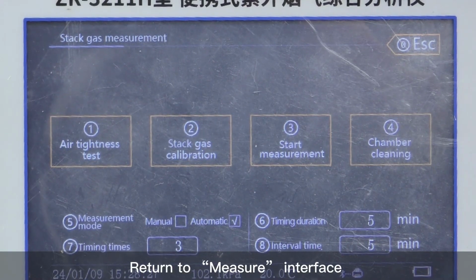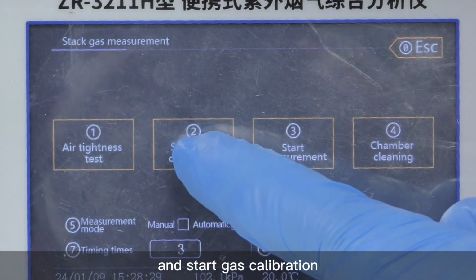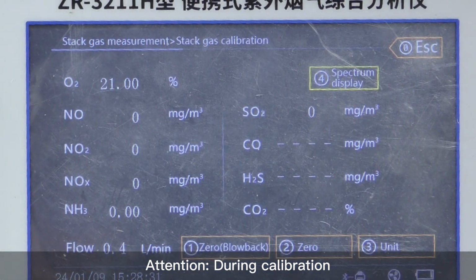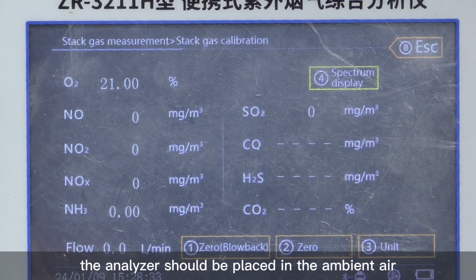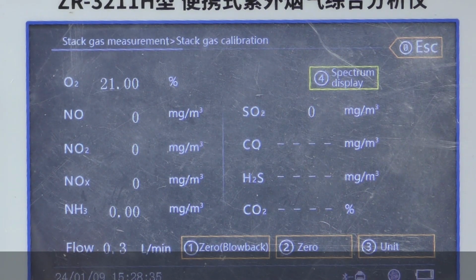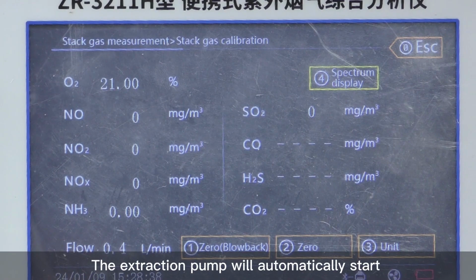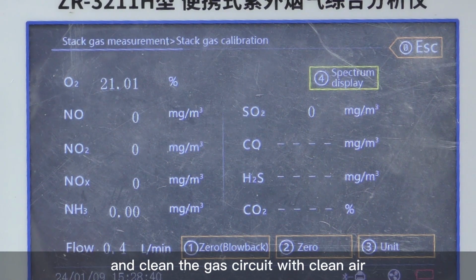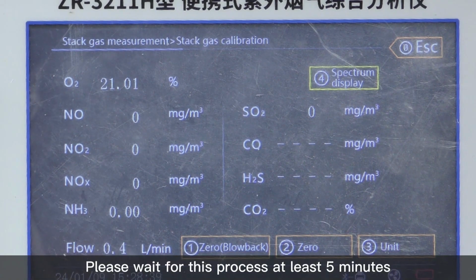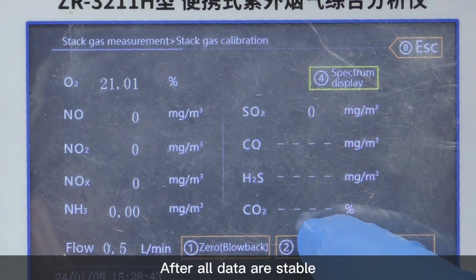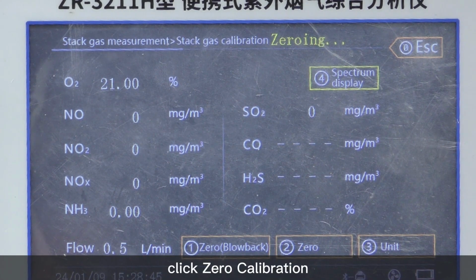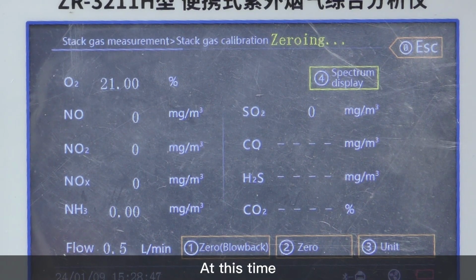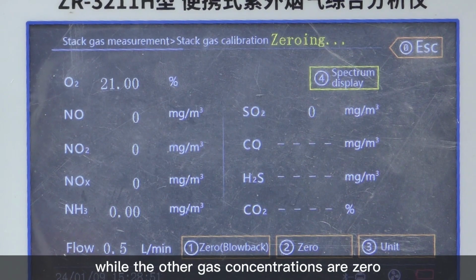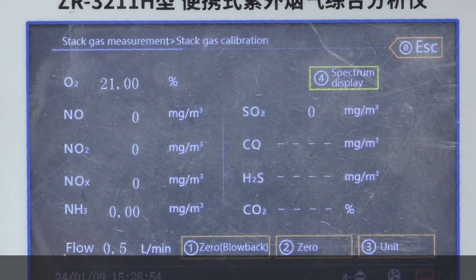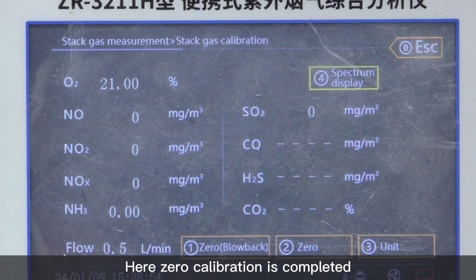Return to Measure Interface and start gas calibration. Attention! During calibration, the analyzer should be placed in the ambient air. The extraction pump will automatically start and clean the gas circuit with clean air. Please wait for this process at least 5 minutes. After all data are stable, click Zero Calibration. At this time, O2 is about 21%, while the other gas concentrations are 0.